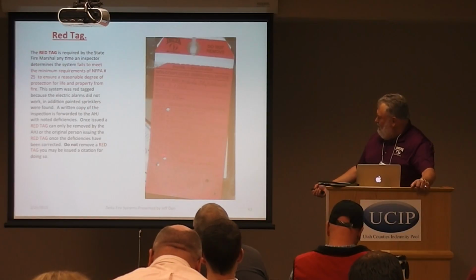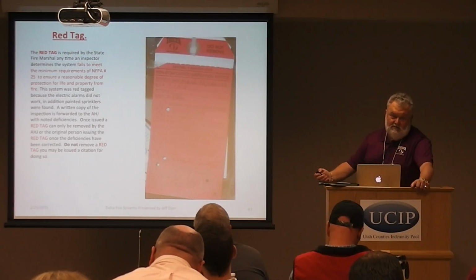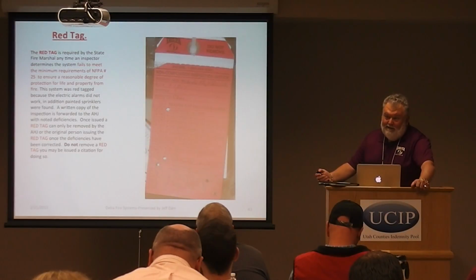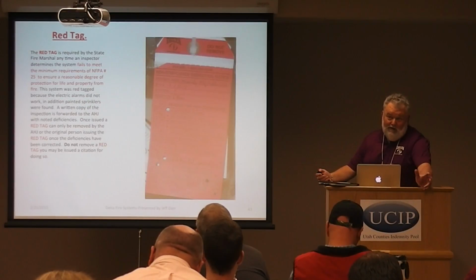In addition, down here, you also would put a note for other, and it said painted sprinkler heads. The only reason he put that on there is that's really not something we will red tag the system for unless a majority of the heads are actually painted. But 1 or 2 will usually tell a maintenance guy, hey, replace these heads or we'll do it for you. If we do it, it just obviously is going to cost a little more.